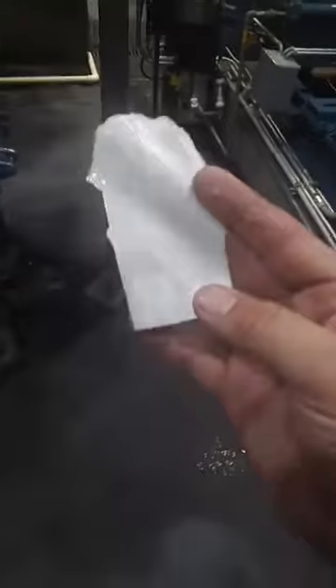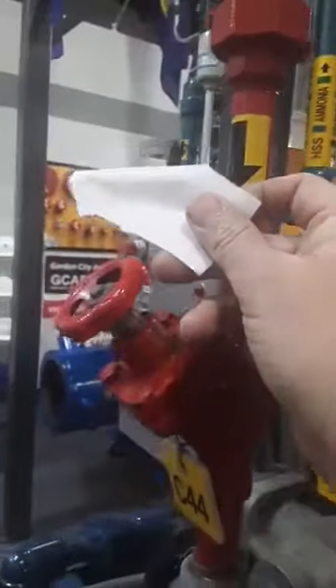I have all these strips together and I know the leak is coming from somewhere around this pumper drum. So I'm going to start putting this litmus paper above certain things that have the possibility of having a leak — because ammonia gas in gas form is going to rise. I'm looking to see if the litmus paper changes color based on a reaction with any ammonia present. As I come around right there — I don't know if the camera is showing this — but instantly when I hit that union, look how pink that is, and where my hand is it's white. Flip it around — boom, right there, instantaneously found the leak.